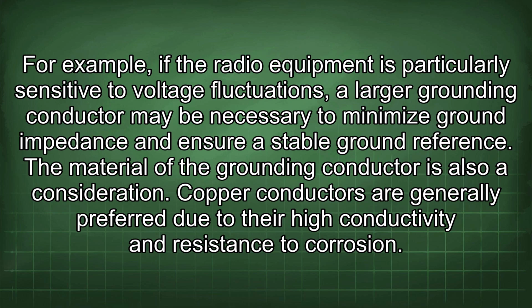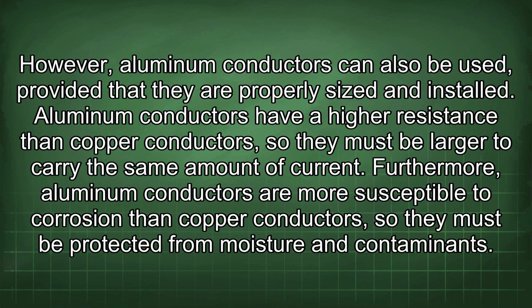The material of the grounding conductor is also a consideration. Copper conductors are generally preferred due to their high conductivity and resistance to corrosion. However, aluminum conductors can also be used, provided that they are properly sized and installed. Aluminum conductors have a higher resistance than copper conductors, so they must be larger to carry the same amount of current.